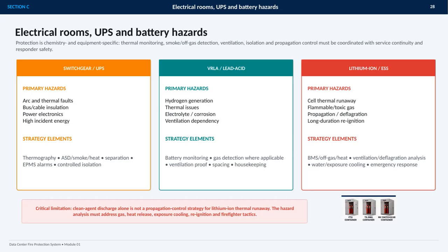This section focuses on electrical rooms, UPS equipment, and battery hazards. The central point is that protection must be matched to the chemistry and equipment involved, while also supporting service continuity and responder safety. A clean agent discharge by itself does not control lithium-ion thermal runaway or prevent propagation.